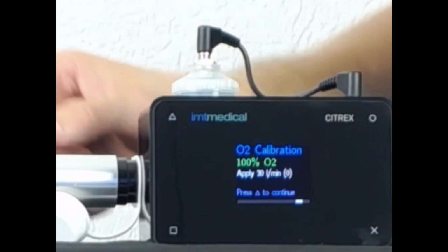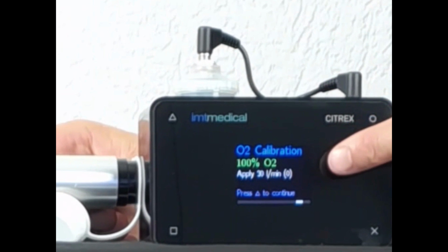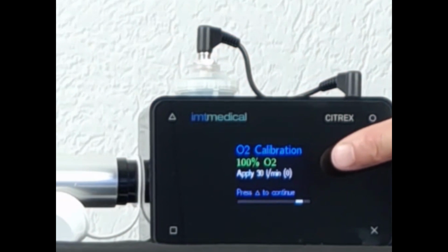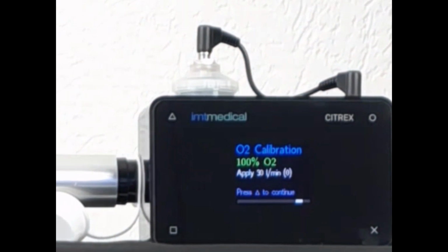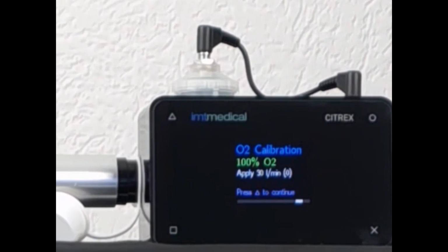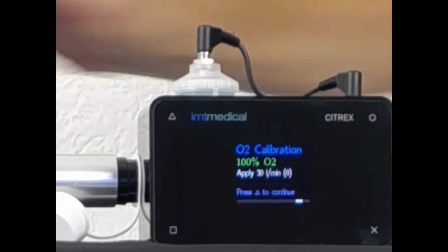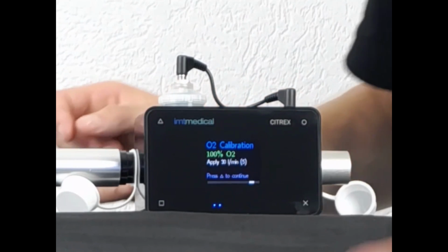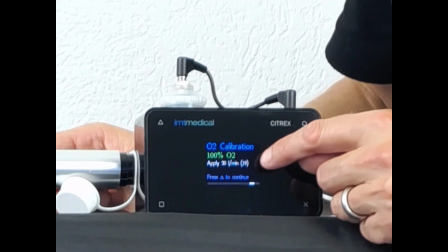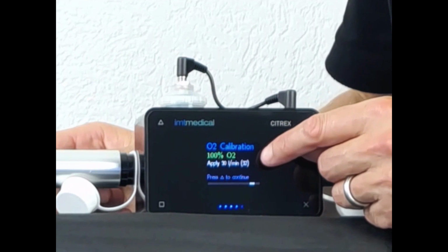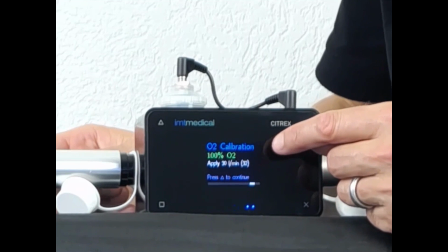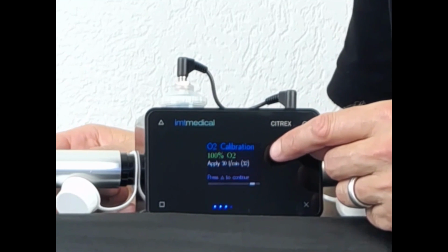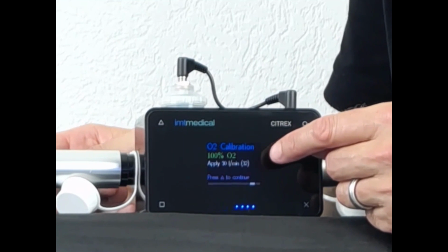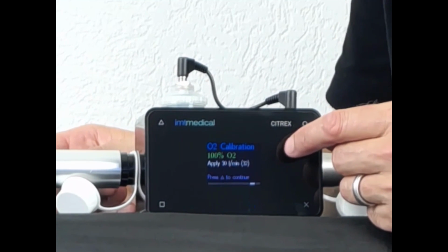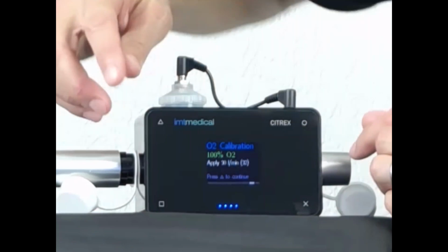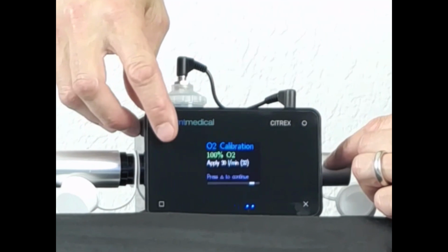I start it, and it tells me to apply 30 liters per minute of oxygen, 100% oxygen flow. I use the service level of my ventilator to apply a 30 liter per minute oxygen flow, which I connect now. So I apply the 100% oxygen flow of 30 liters per minute. Here we see the actual real-time value of the oxygen flow. And I have to stress the point that we really apply an oxygen flow which is high enough. In the neighborhood of 30 liters per minute is a must for a successful oxygen sensor calibration. Then I start the calibration by hitting the triangle.